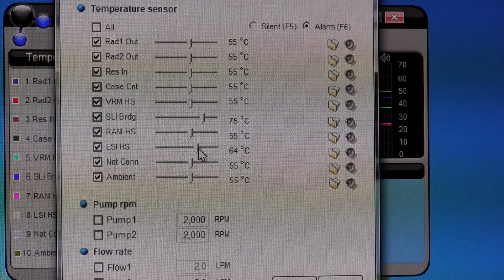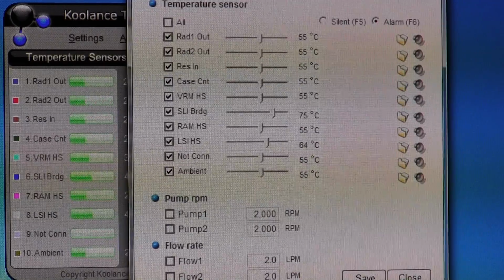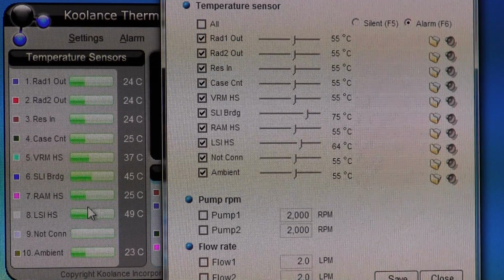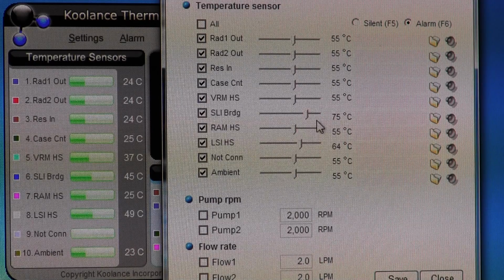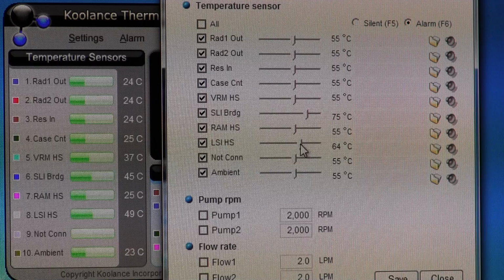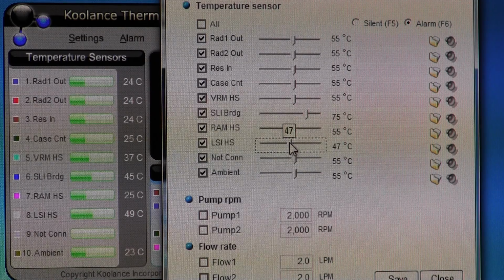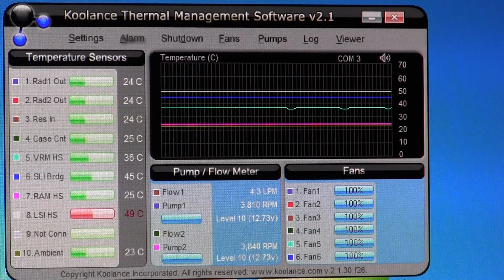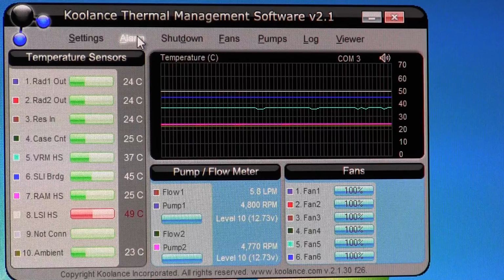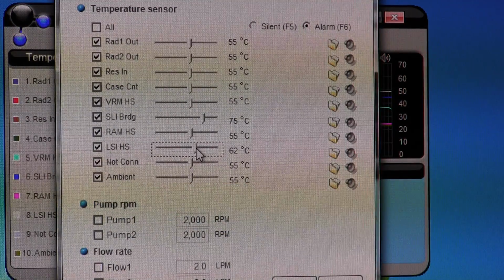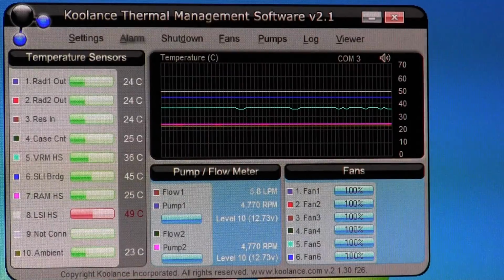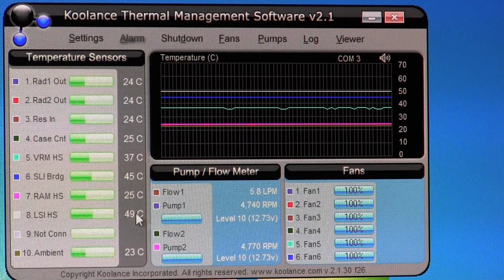I will reduce the alarm setting. Right now the LSI is currently at 49 degrees C. So I'm going to drop this guy from 64 down to 47 and save. So it went to red and it automatically started setting the alarm off for you. So I just changed it back up to 67 degrees.